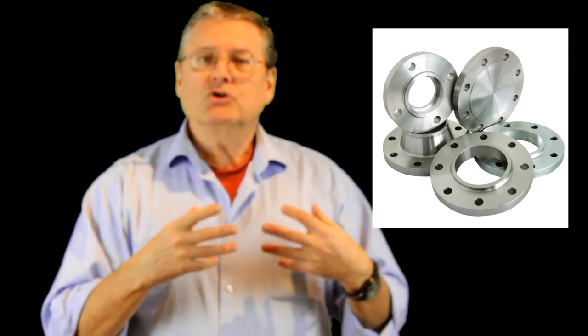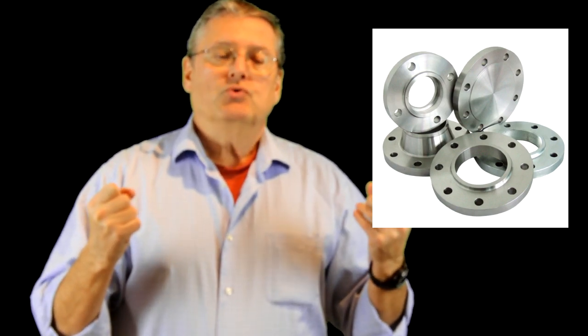So to find out the actual rating of this flange, you need to go to the code, the ASME code B31.3, and you'll see tables in there that will tell you, well, for this class of flange, this material and this temperature, this flange will withstand so much pressure. So a 150 pound flange typically will be quite good for 300 PSI and above. But you need to check for the material and the temperature.